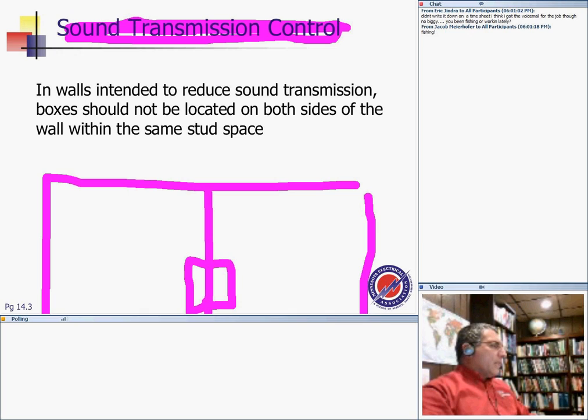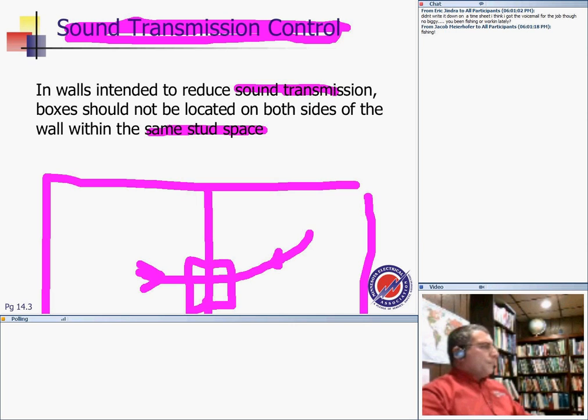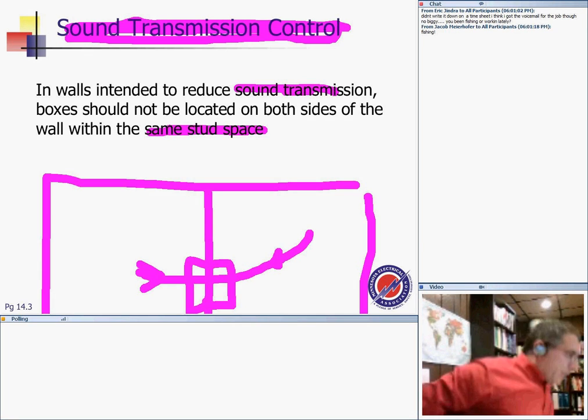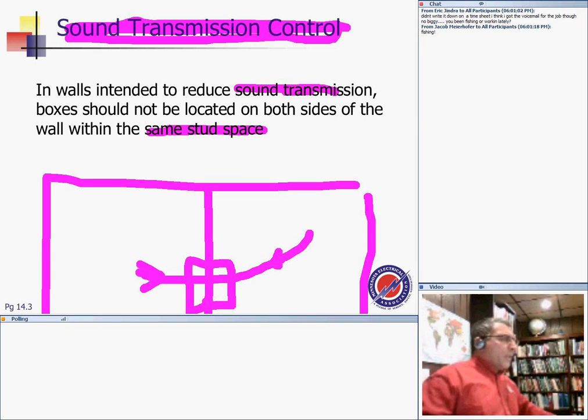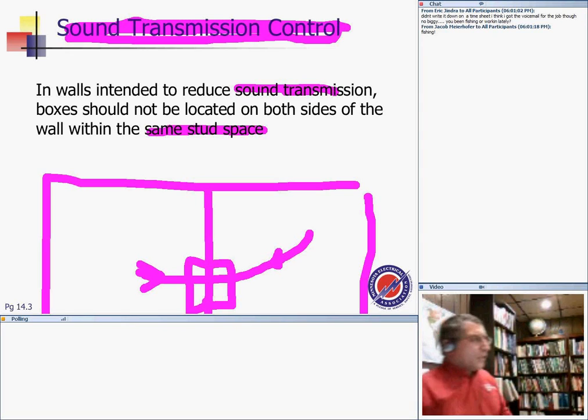The noise from both directions can go from here to here. So for transmission of noises, sound transmission through the boxes, boxes shall not be located on both sides of the walls within the same stud space. So these are mainly for sound control, especially if it's 2 apartments. That's the place where you pay a lot of attention to it.